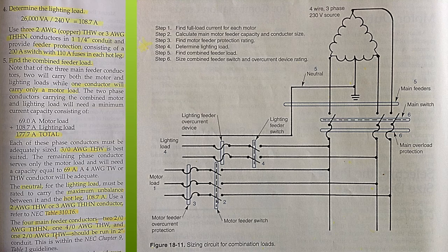The four main feeder conductors, two 2/0 AWG THHN, one 4/0 AWG THW, and one 2/0 AWG THW should be run in 2-inch conduit. This is within the NEC Chapter 9, Table 1 guidelines.